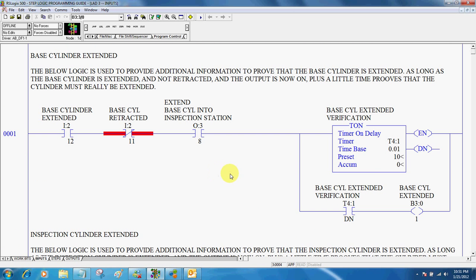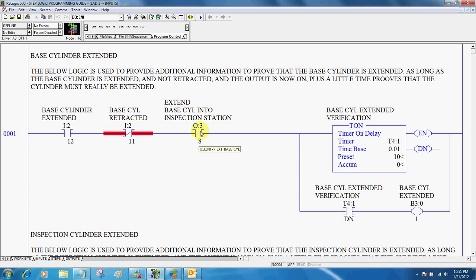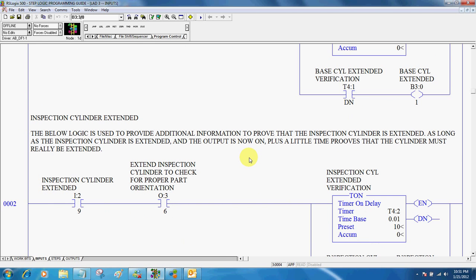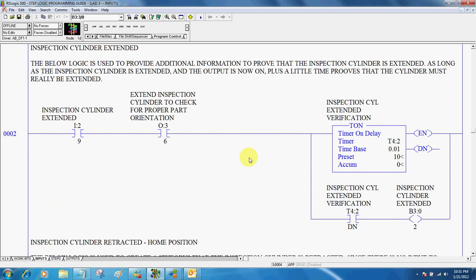Same thing here. Now we want to extend the base cylinder. So if the input is extended and it's not retracted, and the output that tells it to extend, plus a little bit of time, verify that time, and the base cylinder actually would be extended.